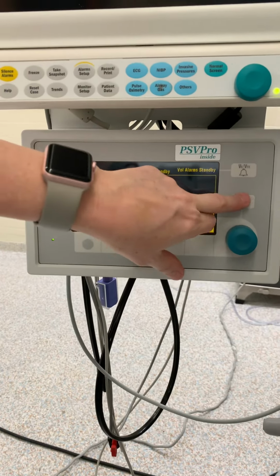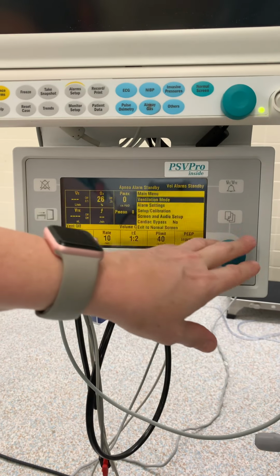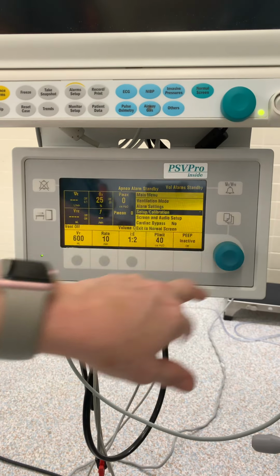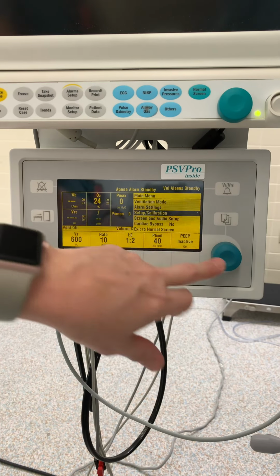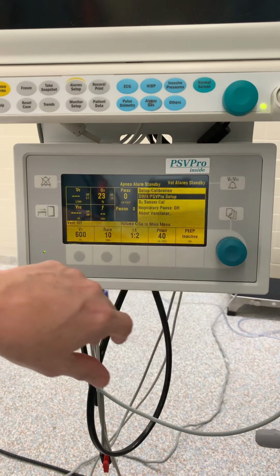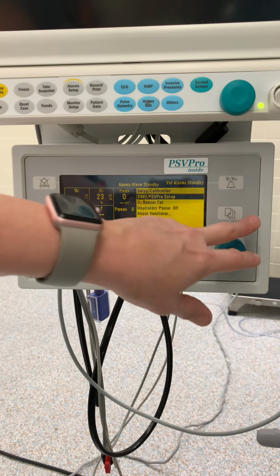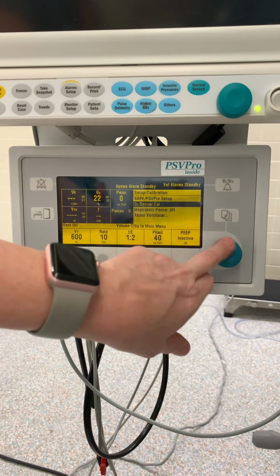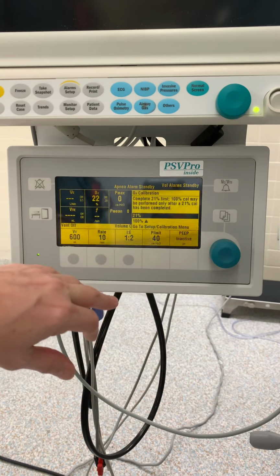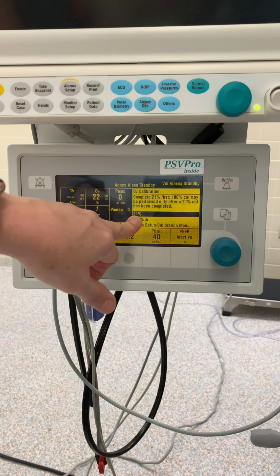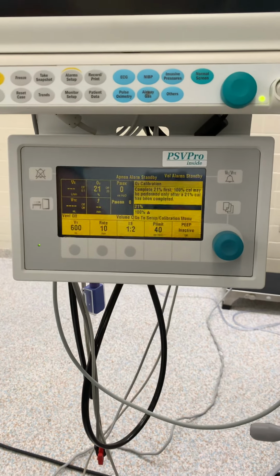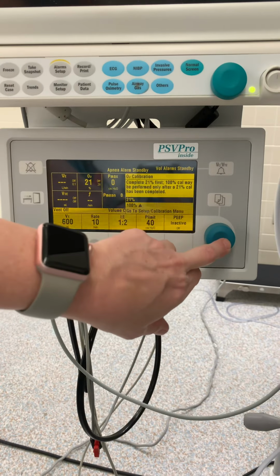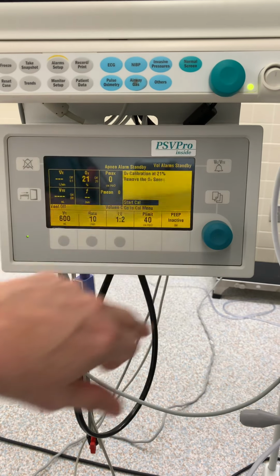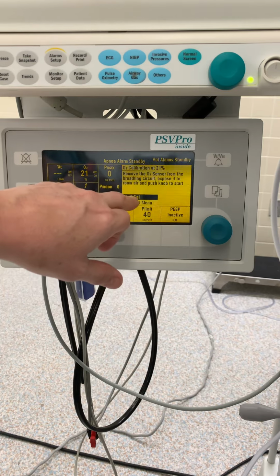The menu looks like 3 pages. You push it, you'll have the option. You scroll down with the green knob, you highlight setup calibration, selected by hitting the green button, and then you want O2 sensor calibration. Again, scroll down, select highlighted by pushing the green button. We want to, first of all, calibrate to 21%. We've got it open to air so it can calibrate. So all you need to do, it's highlighted, is push the green button. It's saying highlighted start calibration. We'll hit the green button.